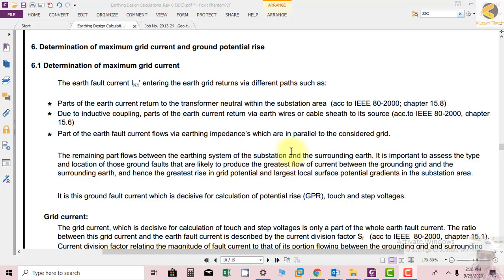Welcome. In this section we will see how to determine maximum grid current and ground potential rise. Both are interconnecting each other. We use the simple Ohm's law formula V = IR, where I is the maximum grid current and R is the ground resistance that we have already calculated.